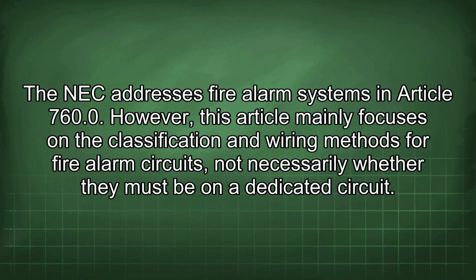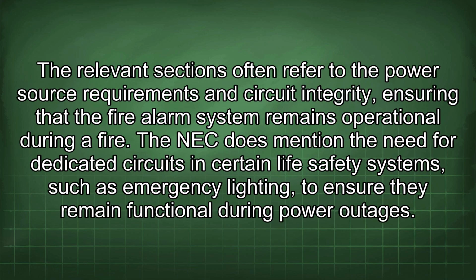The NEC addresses fire alarm systems in Article 760. However, this article mainly focuses on the classification and wiring methods for fire alarm circuits, not necessarily whether they must be on a dedicated circuit. The relevant sections often refer to the power source requirements and circuit integrity, ensuring that the fire alarm system remains operational during a fire. The NEC does mention the need for dedicated circuits in certain life safety systems, such as emergency lighting, to ensure they remain functional during power outages.